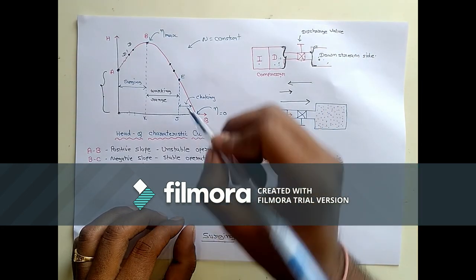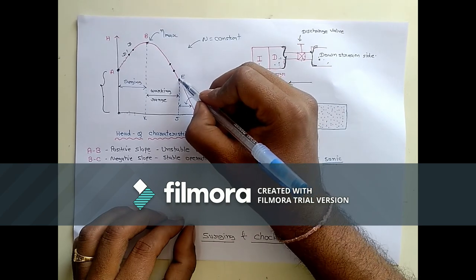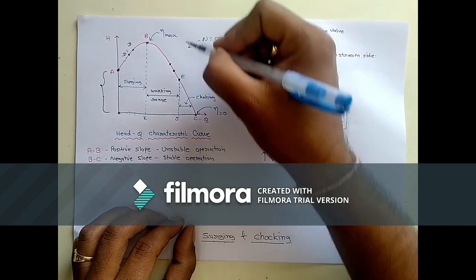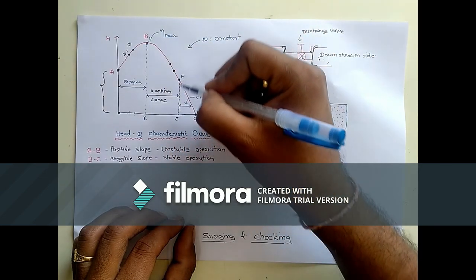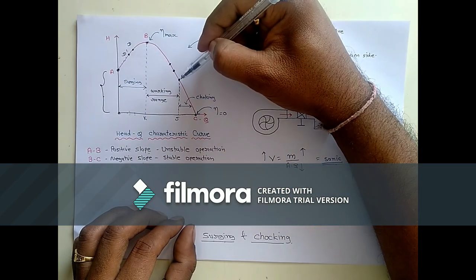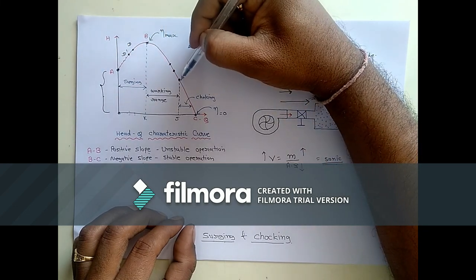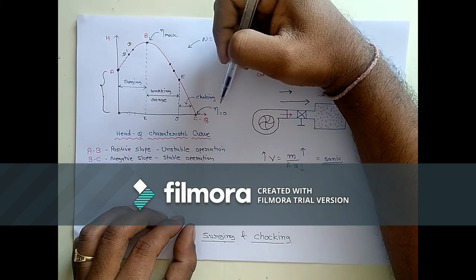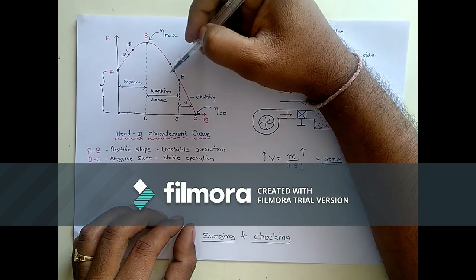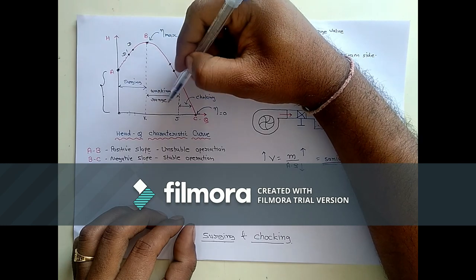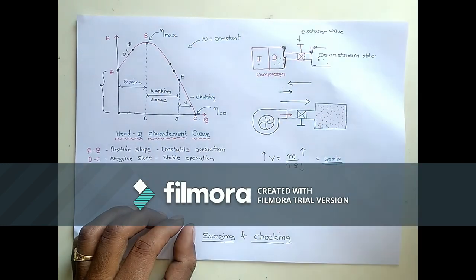Discharge will not increase further even after fully opening the discharge valve. That is known as the choking point in the case of a compressor. So compressors are always designed between points B and E. Beyond B towards A there is a surging phenomena, and after point E the choking phenomena will occur. So B to E is the working range of the compressor.